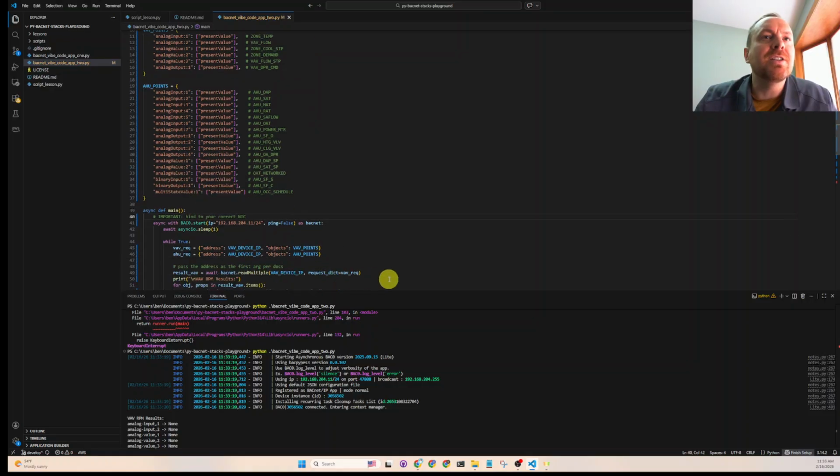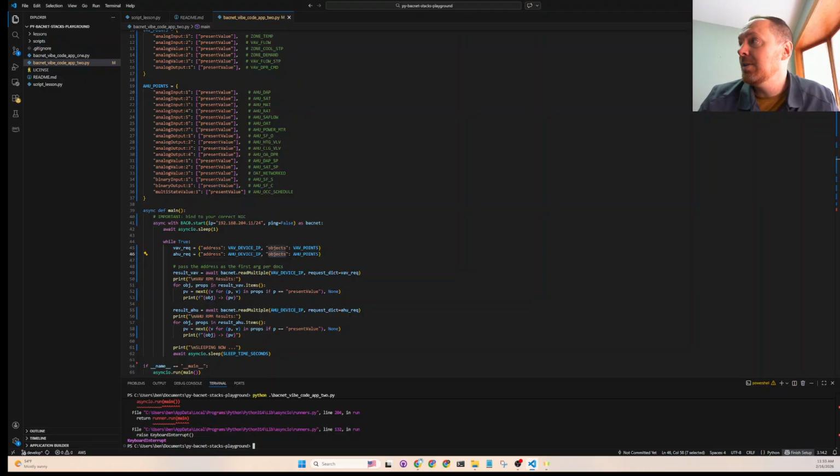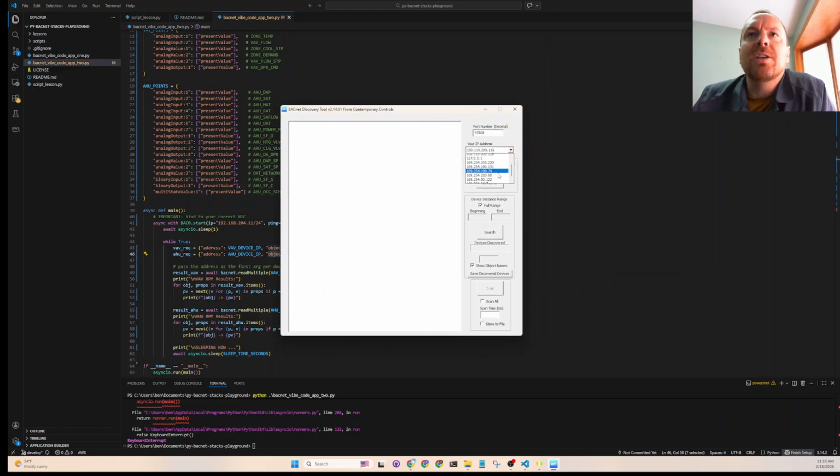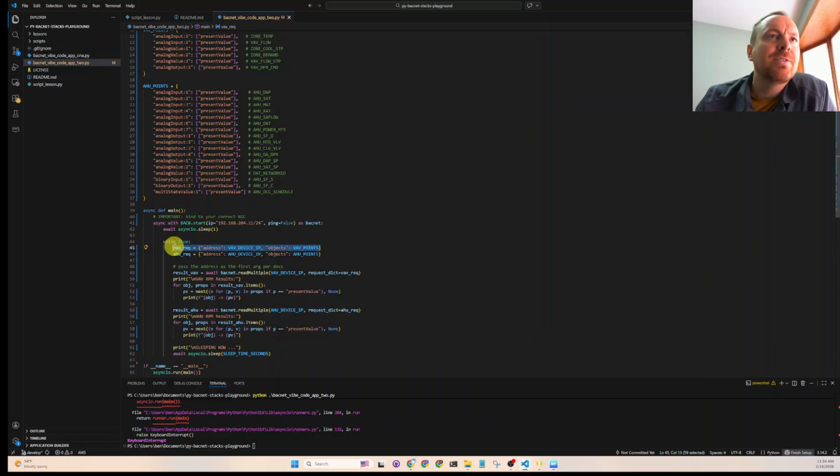I didn't like what ChatGPT did. What it's trying to do is request a point discovery for all of the objects inside of the device, but it doesn't know the BACpypes API well enough to be able to do that. So when I go here, this is my same NIC card, and I have to define another BACnet. It's doing a Who-Is right now. And then when I do my fake air handling unit, that's an object discovery right here. So it's doing that through here, which I don't think we want to do.